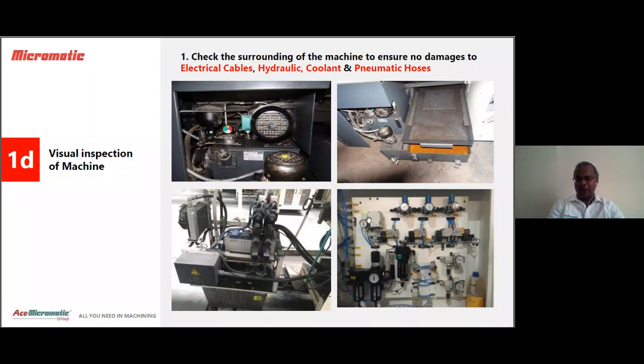Fourth photo in the bottom, we have shown the pneumatic area, because the background of this plate is an ideal place for a rat to settle down. So first you have to check whether any movement of a rat has been identified. Then it is probable that it will be inside the machine or outside the machine. Some cloth can be pulled up from some other area, and they can hide there. So please check all the areas for any possible damage caused by rats.